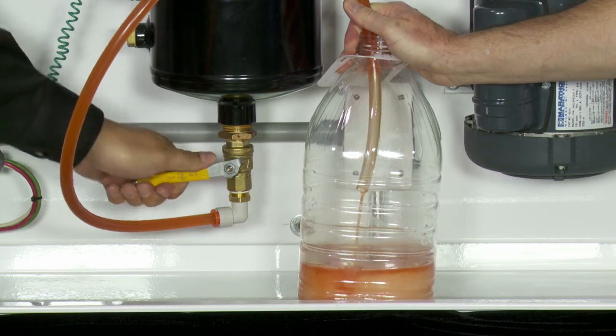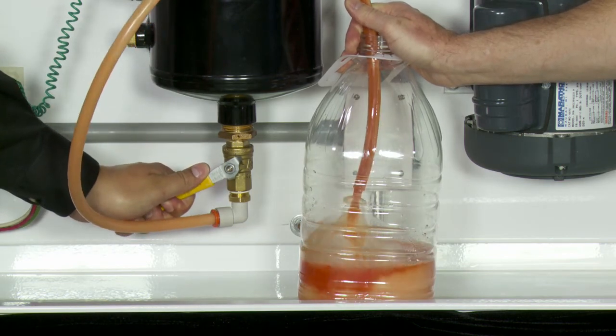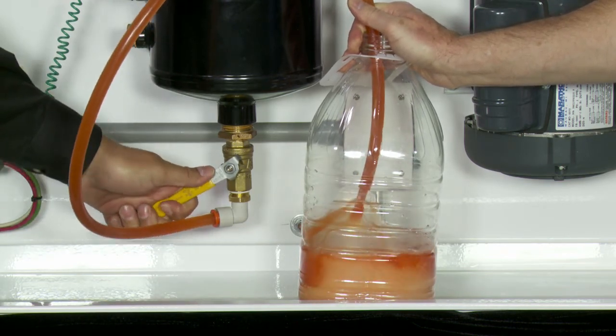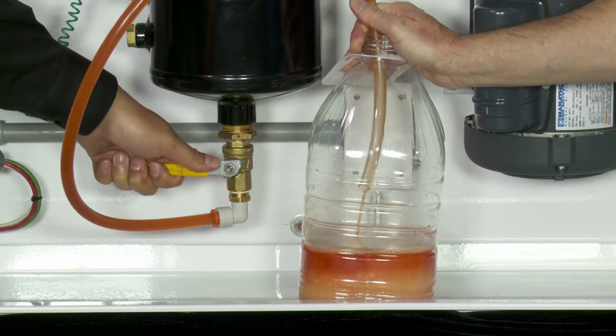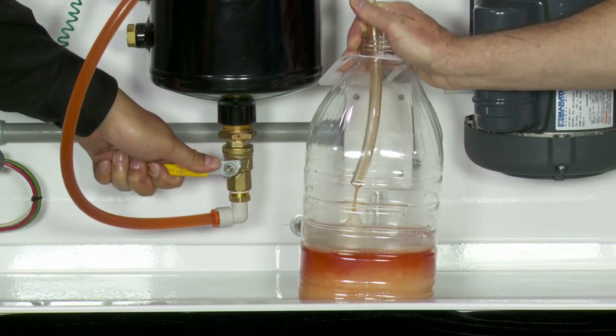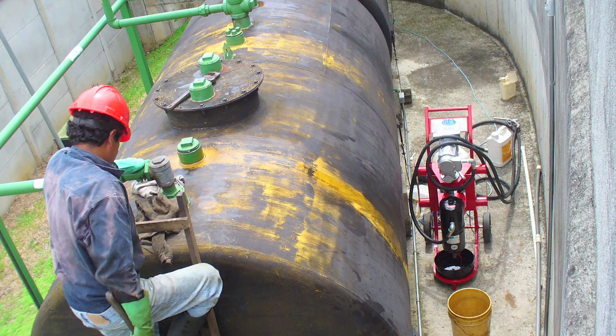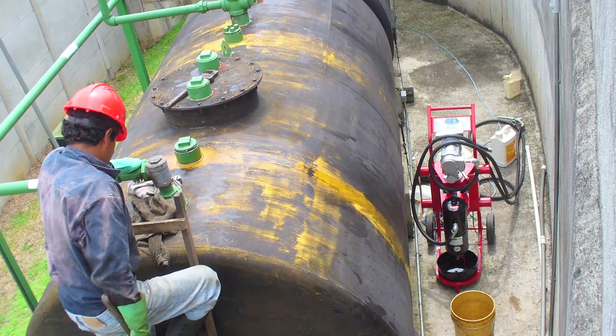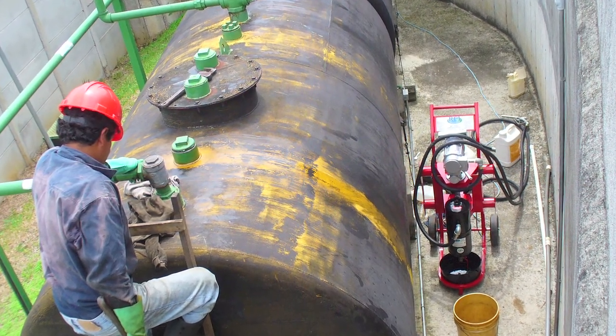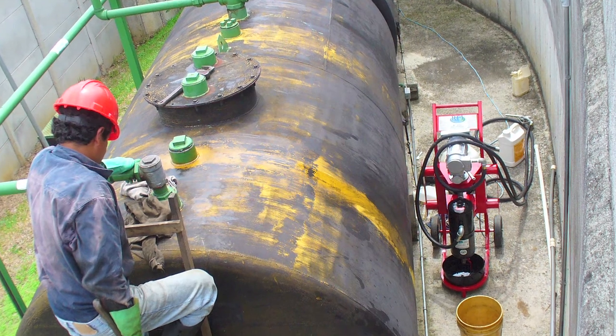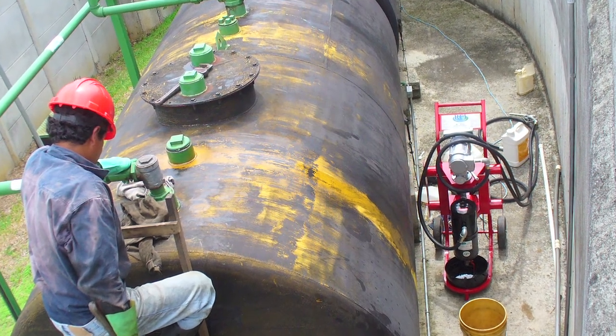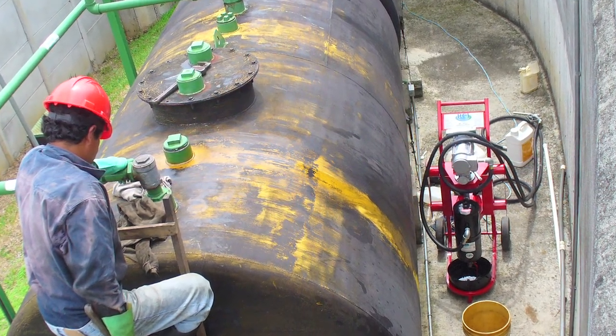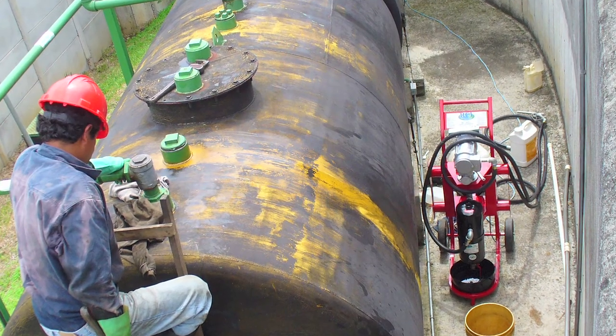Thus preventing the formation and accumulation of water and sludge buildup on the bottom of your fuel tank, while maintaining your fuel in pristine condition. If you're installing the FRS system on an existing fuel tank that is extremely contaminated and has a sludge buildup on the bottom, we strongly recommend having the tank professionally cleaned prior to the startup of your fuel maintenance system.